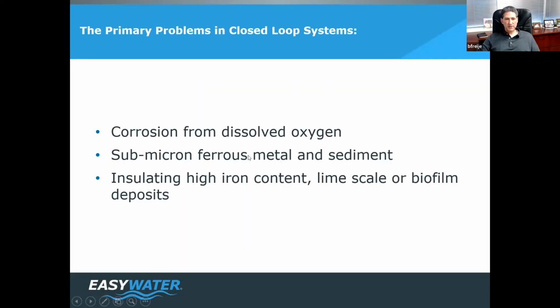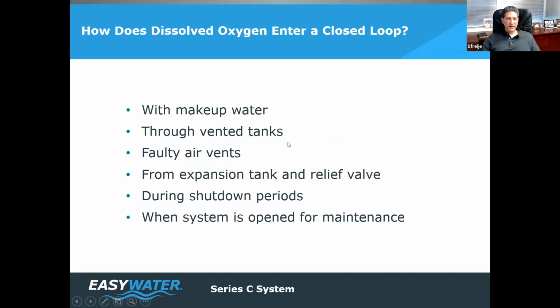Every closed loop system you've ever been involved with, chill, hot, heat pump, has one primary problem: corrosion caused by dissolved oxygen. That problem causes all the other problems. Sometimes I'll ask an end user like a hospital or a manufacturer, so what's your closed loop water look like? Well, it's kind of blackish, rusty color. Well, what is that? It's metal that comes from corrosion caused by dissolved oxygen. So where does all the dissolved oxygen come from in real time?